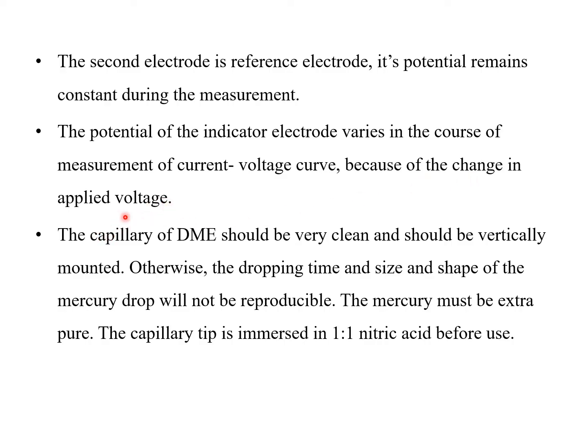There are some precautions to take when using a dropping mercury electrode. The capillary should be very clean and vertically mounted; otherwise the dropping time and the size and shape of the mercury drop will not be reproducible. The mercury must be extra pure. The capillary tip should be immersed in 1:1 nitric acid before use.